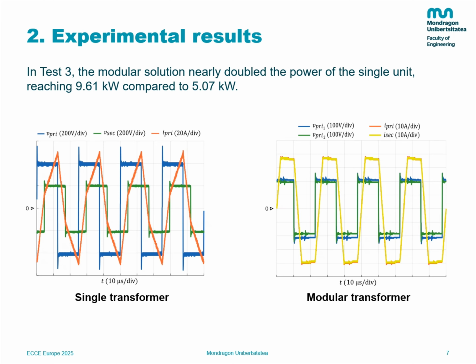In test 3, the modular solution nearly doubled the power of the single unit. This is explained with the transformation ratio. In the case of the single transformer, this value is 1, while in the modular transformer it is 2. Also, in the figures below, we can observe that on the right, in the modular transformer, the AC primary side voltages and secondary side currents are shown. These are the parameters that are shared between each module due to the series parallel connection.